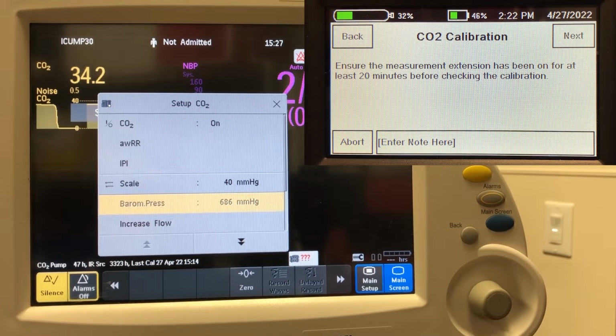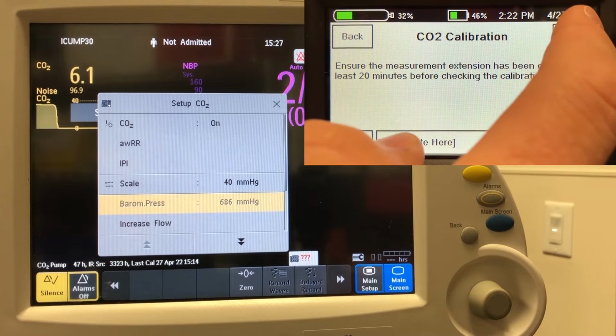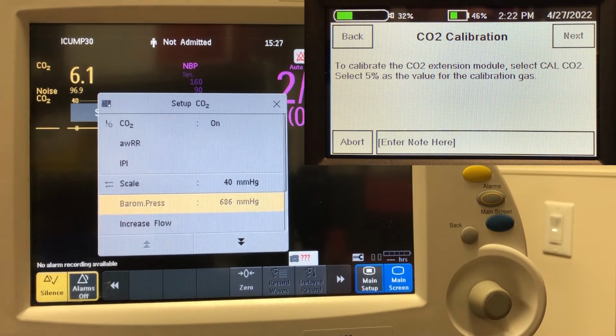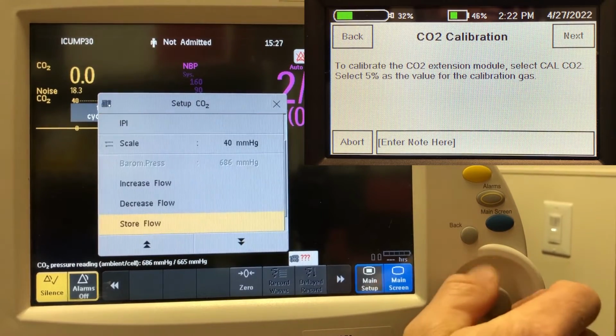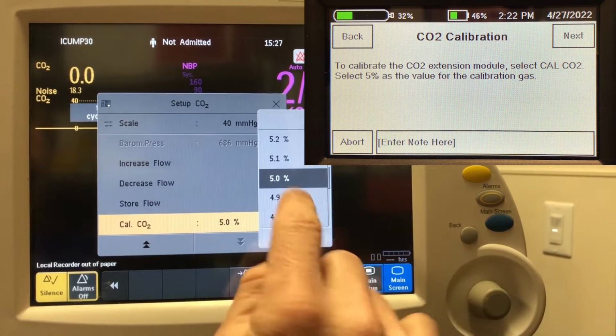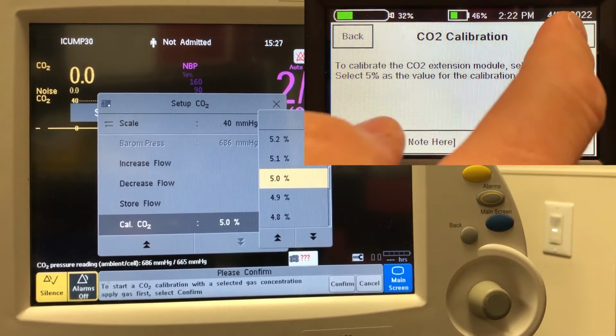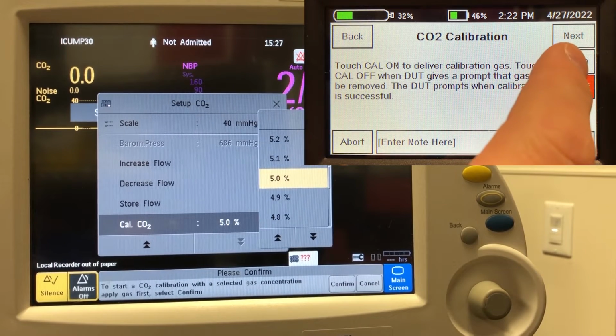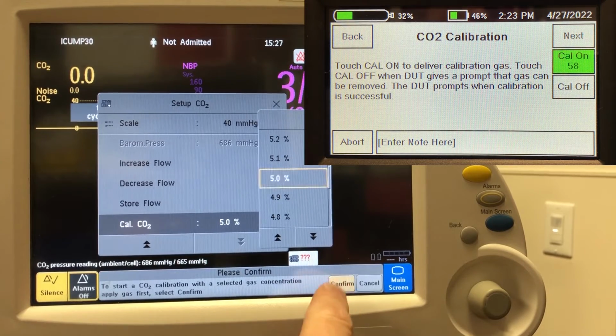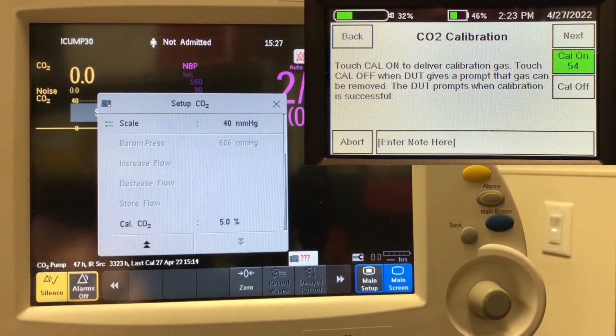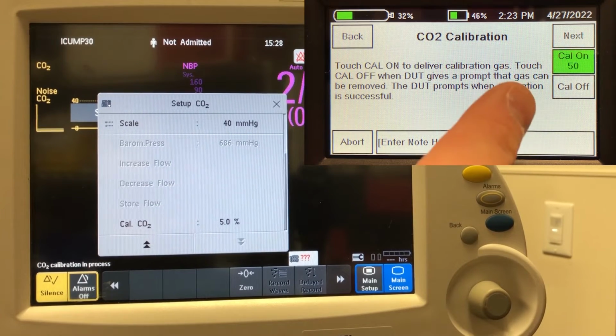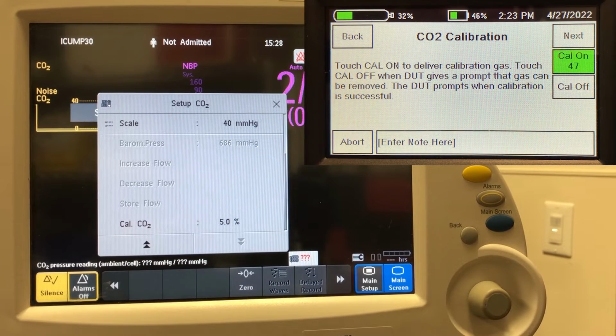Now we're going to do the gas calibration, and it tells us to make sure that the monitor or the extension module has been on for at least 20 minutes, so it's up to full temperature. We're going to go into Cal CO2, select that, select 5%, and then a Smart Tank on the next page. We have the control of Cal gas. Turn the calibration gas on, and we can hit confirm over here. Now the monitor is going to start running through its calibration procedure, and the Smart Tank is controlling the calibration gas flow. So the Smart Tank in this mode is feeding just enough gas to the gas monitor so it's not wasting much calibration gas through the exhaust port inside the Smart Tank.